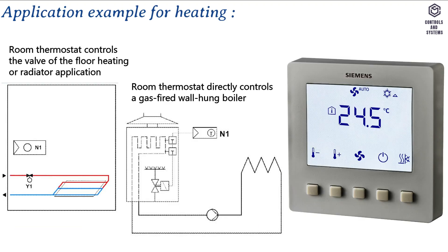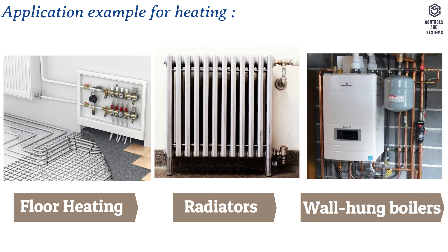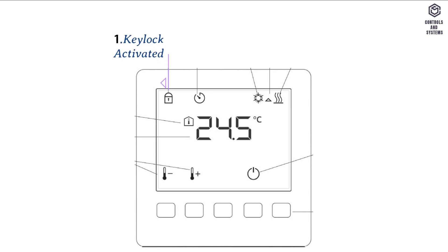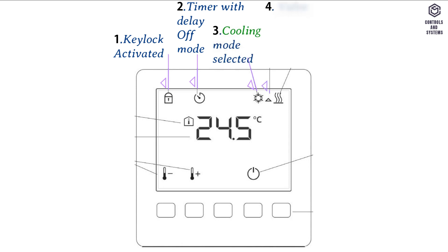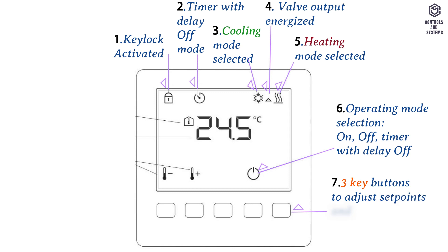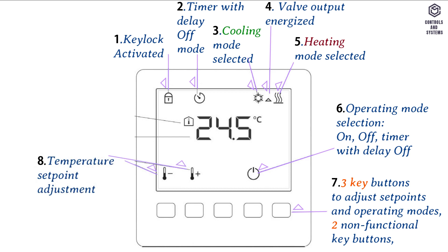Application examples for heating include floor heating, radiators, and wall-hung boilers. Operating and setting elements: (1) key lock activated; (2) timer with delay-off mode; (3) cooling mode selected; (4) valve output energized; (5) heating mode selected; (6) operating mode selection — on, off, or timer with delay-off; (7) three key buttons to adjust set points and operating modes, while two non-functional key buttons are required for parameter mode and other access; (8) temperature set point adjustment; (9) temperature value; (10) room temperature.